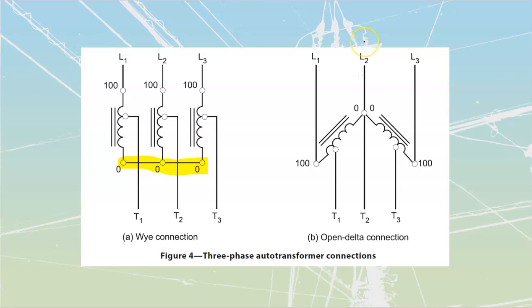These autotransformers are also not going to be rated to give us continuous duty operation. Continuous duty would mean that we're constantly starting. First of all, what we covered in the code earlier tells us that we're not allowed to run anything from any of our starting methods permanently. They have to automatically switch out. And secondly, it's just going to cause overheating. They're designed as undersized because they're only going to be operated for a short amount of time.